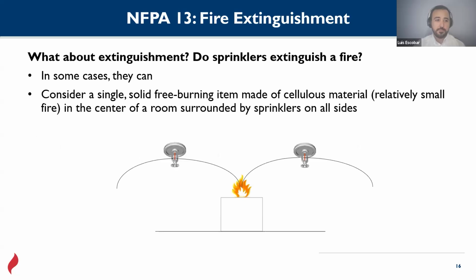Do sprinklers extinguish a fire? In some cases, they can. As we previously saw, not all cases apply, right? If there are two fires, it's impossible for the sprinkler system to work properly. Here's an example. Consider a single fire. It could be, I don't know, a couple of paper sheets burning or a wood construction chair that is on fire. Obviously, it's considered a low to medium heat release. So a well-designed fire sprinkler system won't have any problem suppressing that fire.